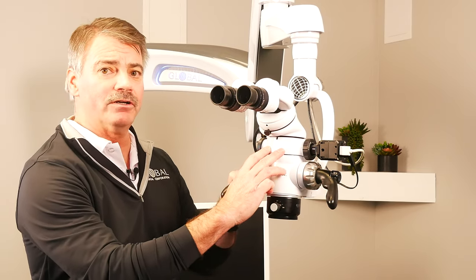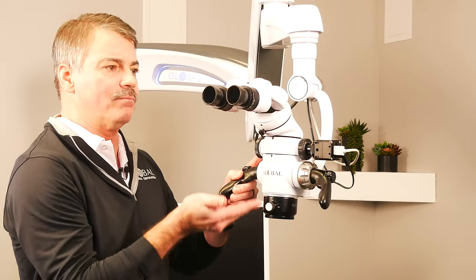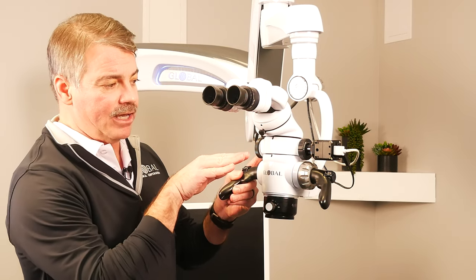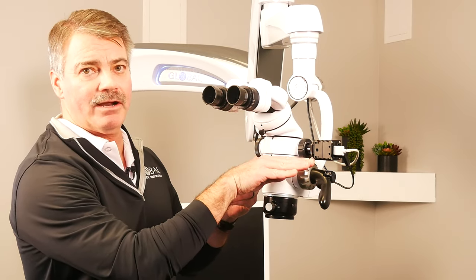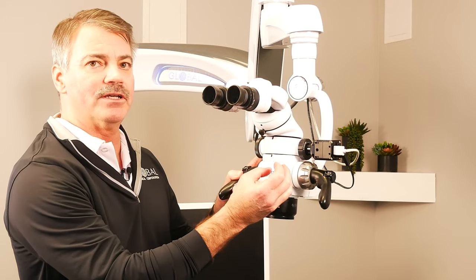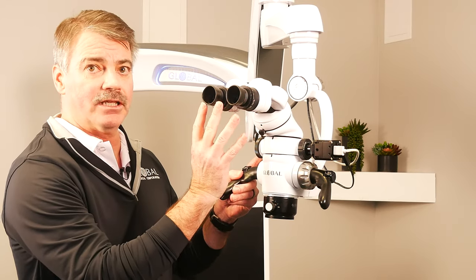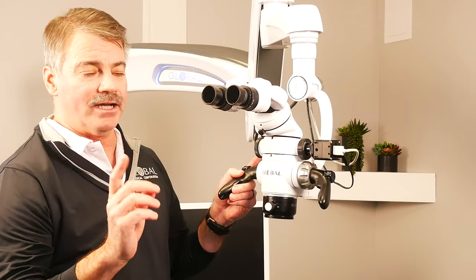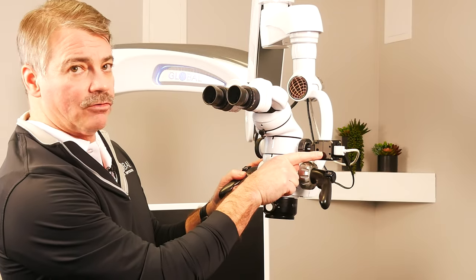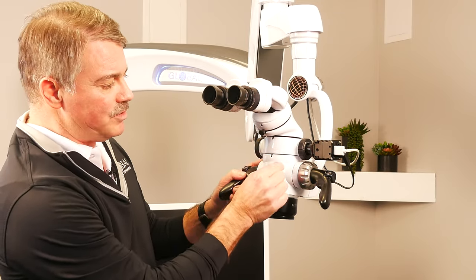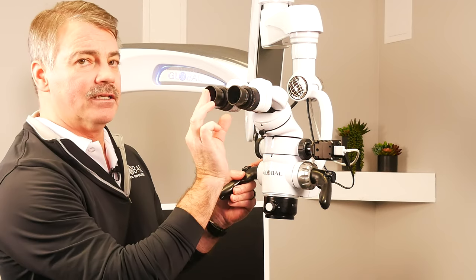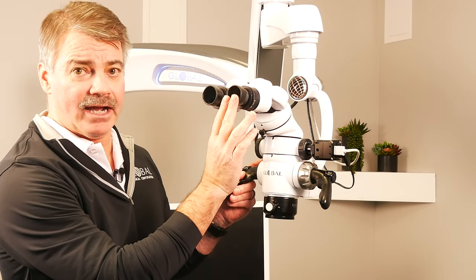What this beam splitter does is take the light being reflected back up to the operator's eye and send 50% of it to the camera system, so it gets the same image as what the operator sees in the binoculars. Keep in mind, if the camera system is on the right-hand side, since it's only seeing one path of light, the image is only going to show what the operator's right eye sees.